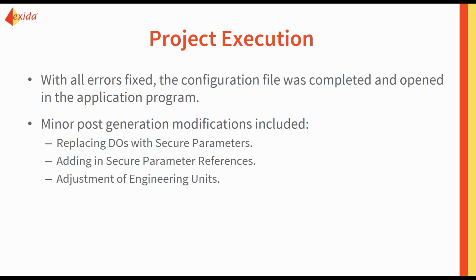And with the secure parameters, that's actually something that is possible in the program, but again, this SIL verification was done without knowing that the program would be used, and so that needed some minor massaging afterwards. So what are the results?